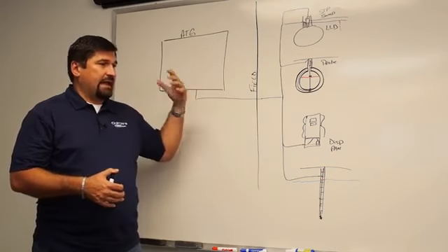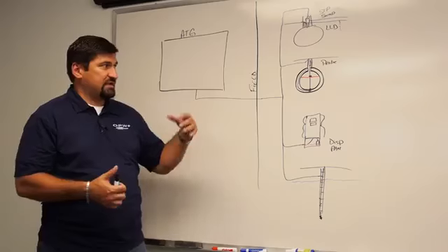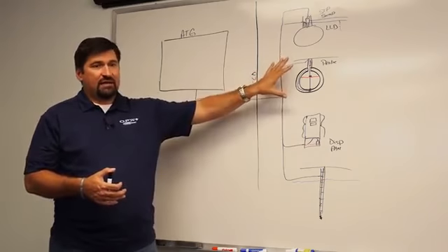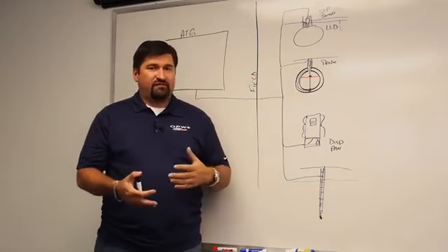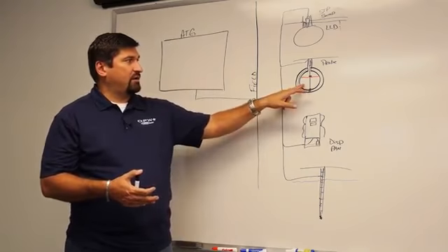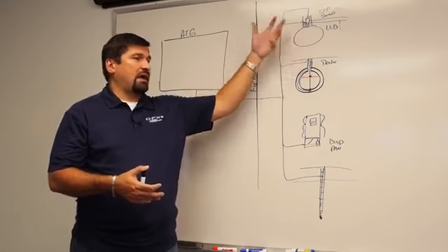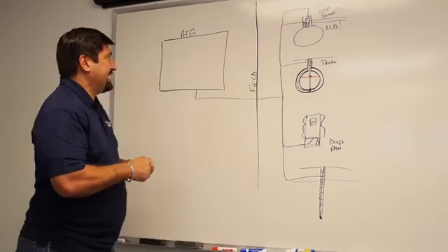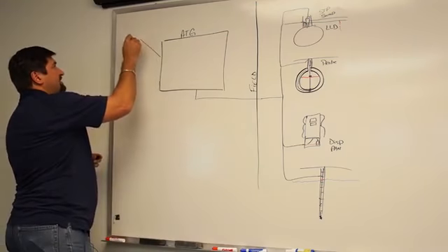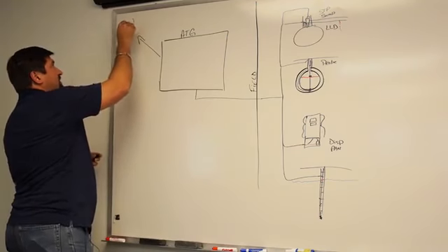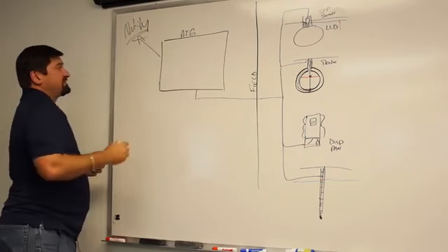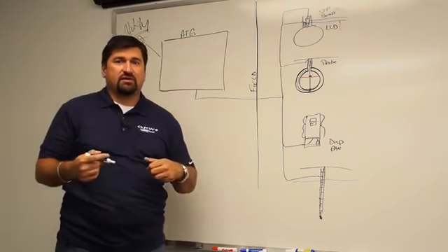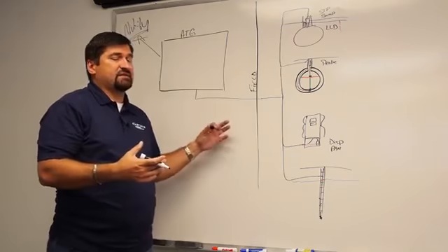So think about the ATG as your controlling source. It's listening, it's controlling everything, but at the point where it finds a problem, let's say I have water in a tank, or a line leak, or fuel in an STP, it also has the ability to notify somebody outside of the site to make sure they're aware that there is a problem at this facility.